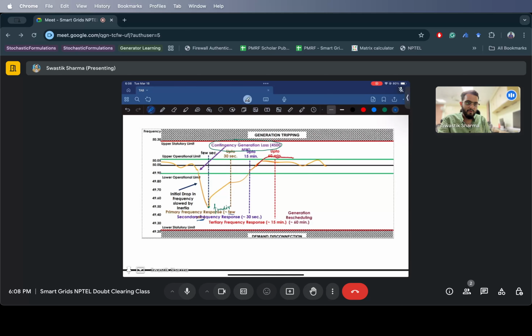What the primary response did was your governor output was controlled, and it continues for about 30 seconds. If the frequency is not brought back within 30 seconds, they now kick in the secondary frequency response. In this, they control the droop characteristics to bring it back to the stable operating point, right? And that is what they did. This continues for another 15 minutes.